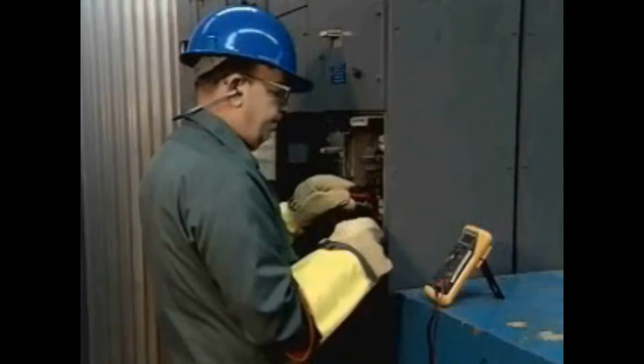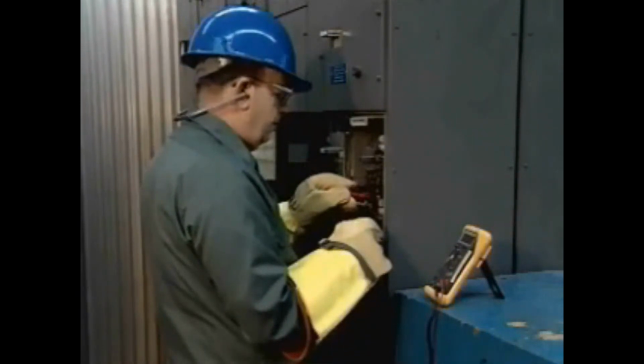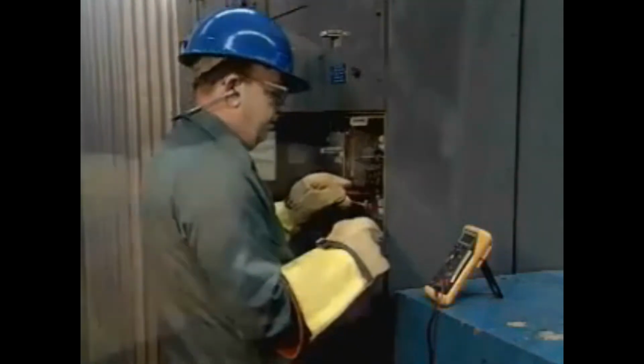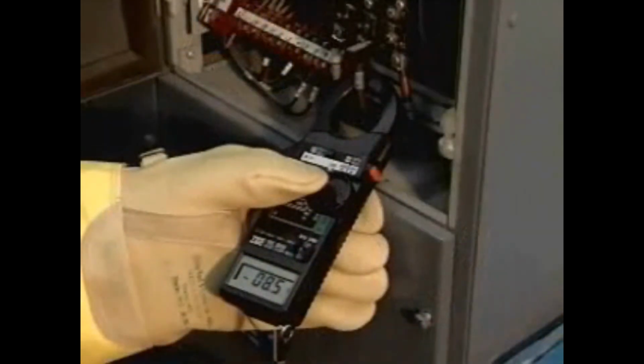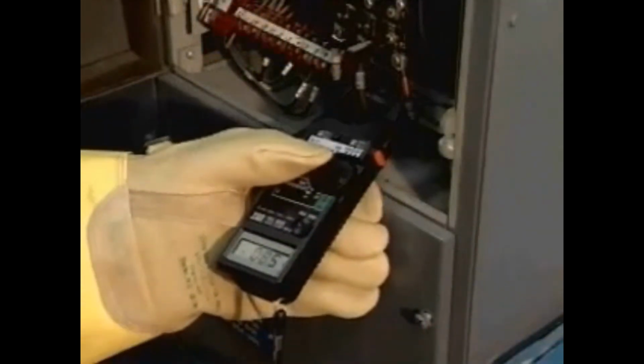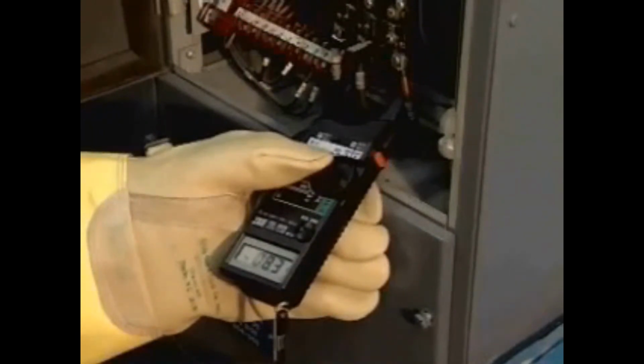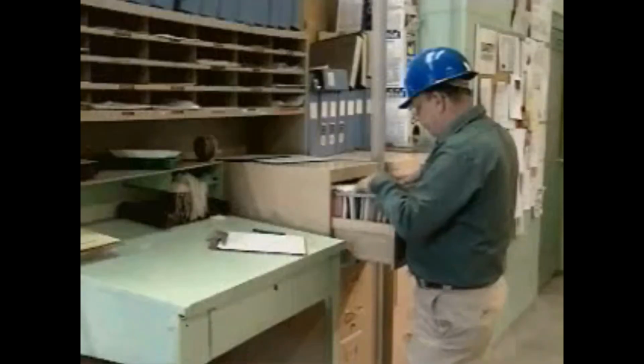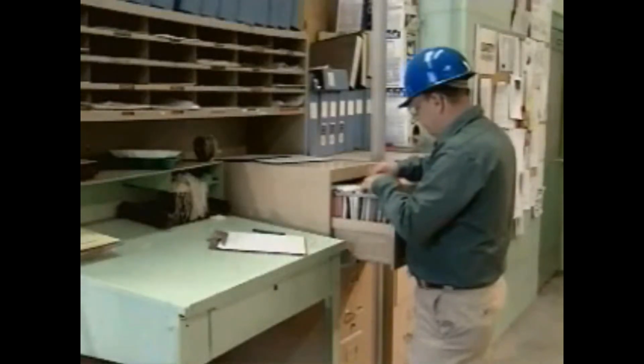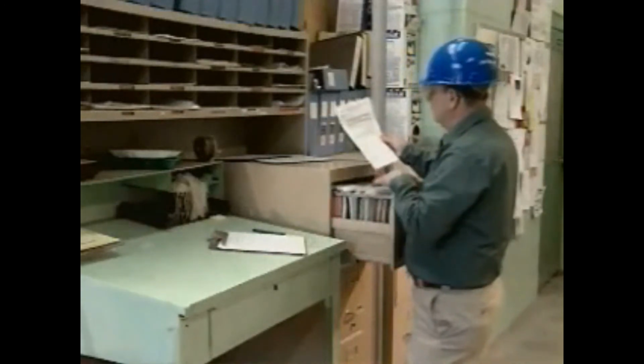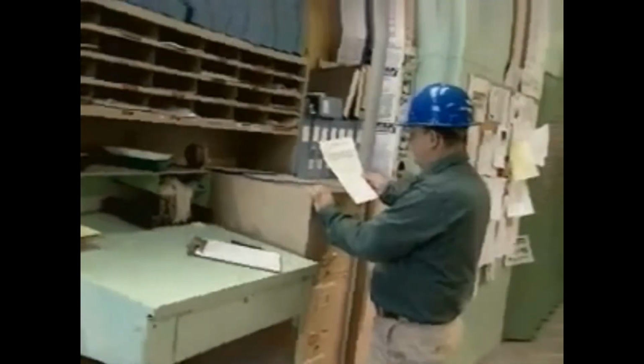Another critical part of a preventive maintenance program is measurement. Measurement allows you to accurately assess the functioning of various aspects of the motor. These aspects include current, temperature, and vibration. To determine if your equipment is functioning properly, it is not enough to take measurements alone. When you take measurements, you must compare them to previous measurements in order to track equipment performance.